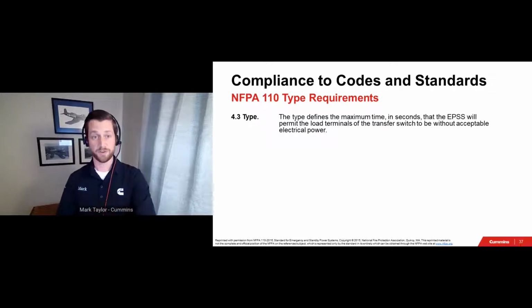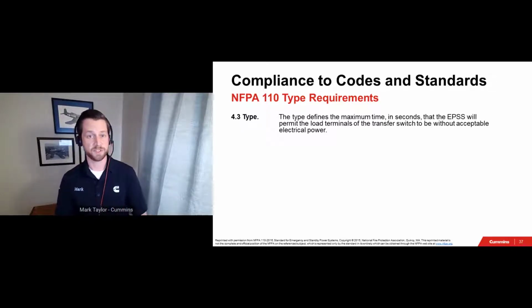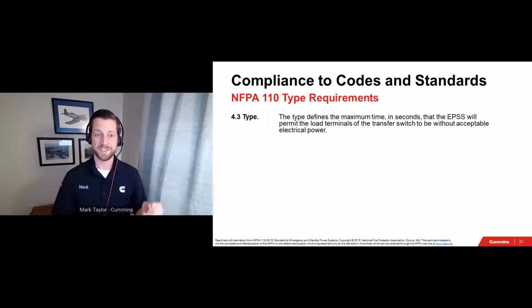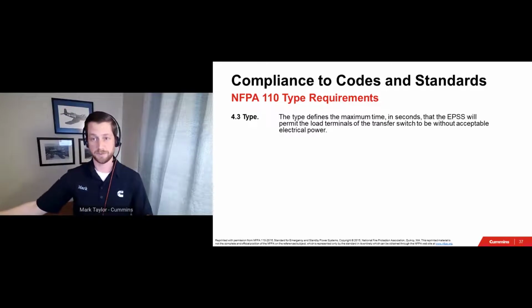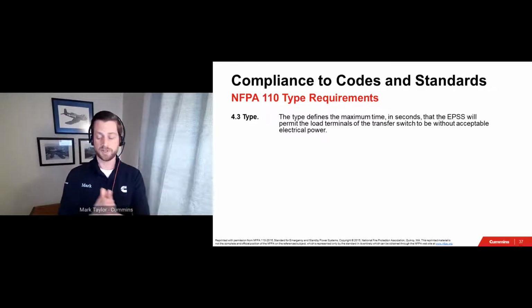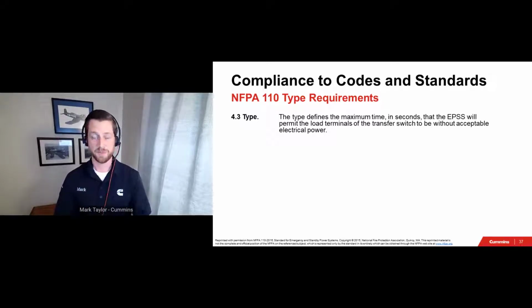We discussed NFPA 110 earlier in this presentation, but you all know we can't go along without talking about it some more. This time, I'll be discussing NFPA 110's type of an emergency power supply system, or EPSS. Type is the maximum time in seconds that the EPSS will permit the load terminals of the transfer switch to be without acceptable electrical power. And just to reinforce this point, this requirement is not just for the generator set start time, and it's also not measuring from generator start all the way to every single load is back on and everything's fully functional all the way down to every receptacle, but is the time from power out to acceptable power at the load side of the transfer switch of the EPSS.